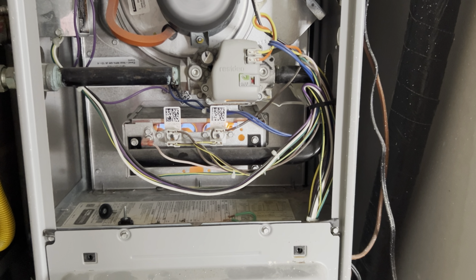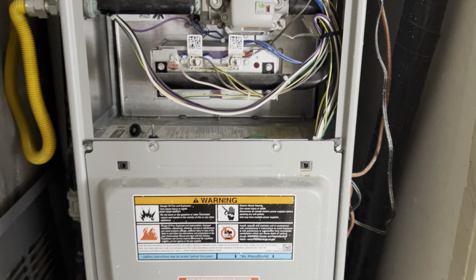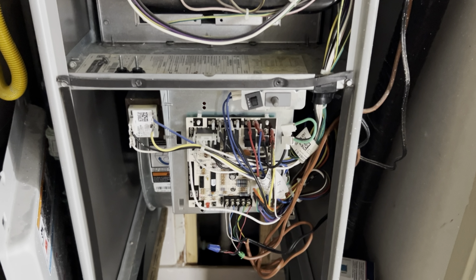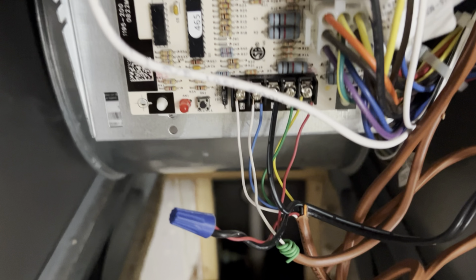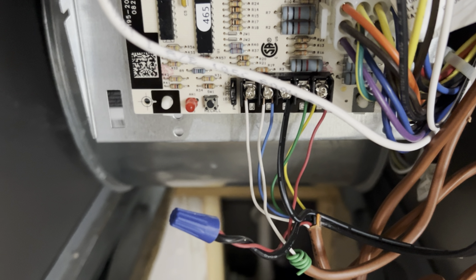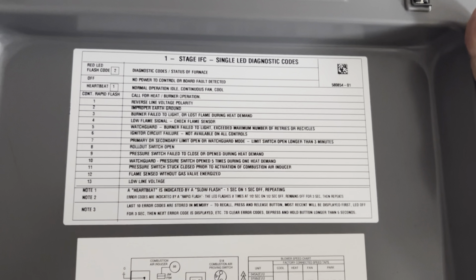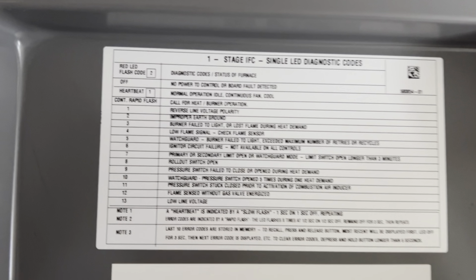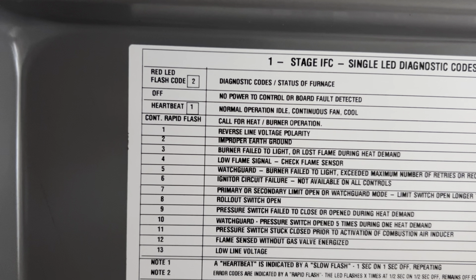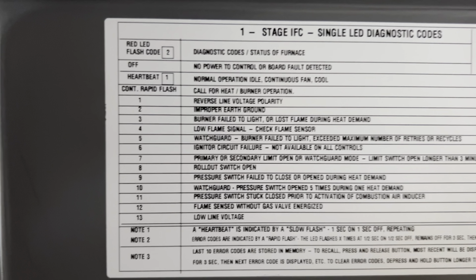The unit will attempt an ignition cycle 3 times before going off on ignition failure. The unit does have an alarm code indicated by this red LED light. The number of blinks indicate the problem that the unit has, and on the back of this door cover, it will tell you what blinks mean and what to look for in order to make the repair necessary.